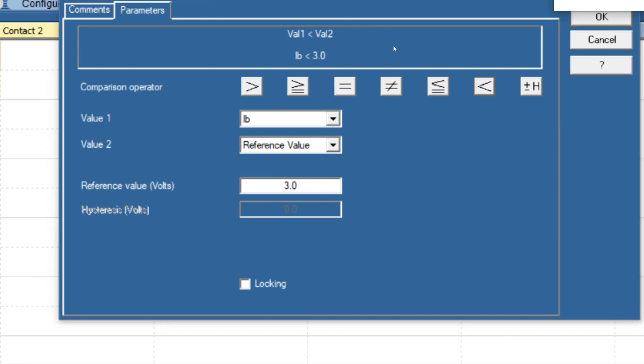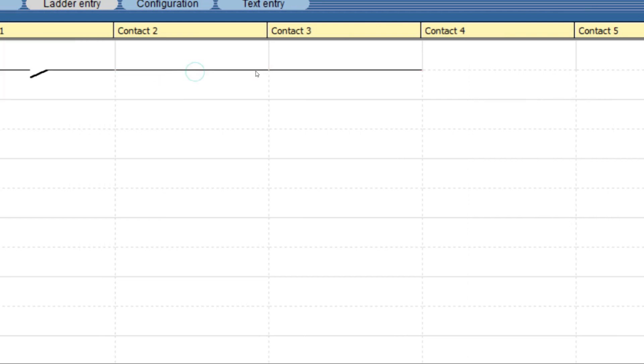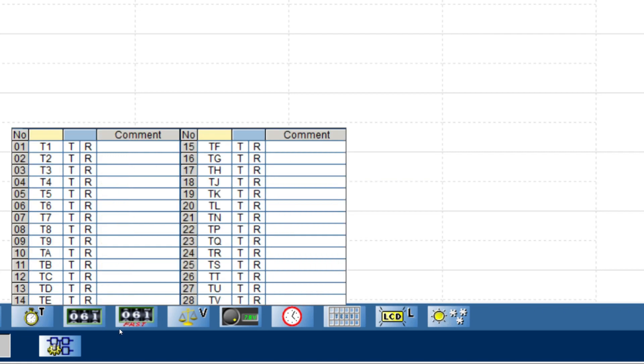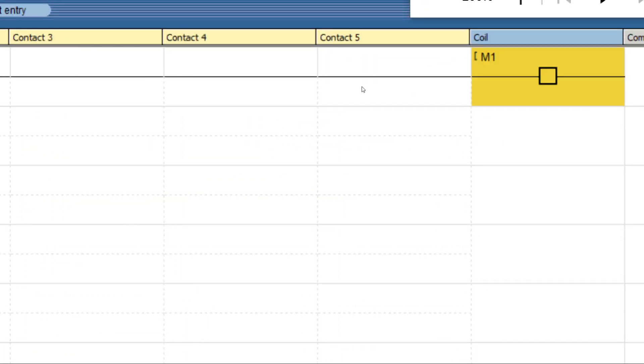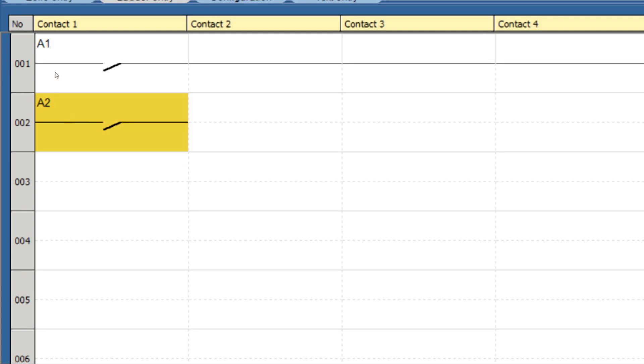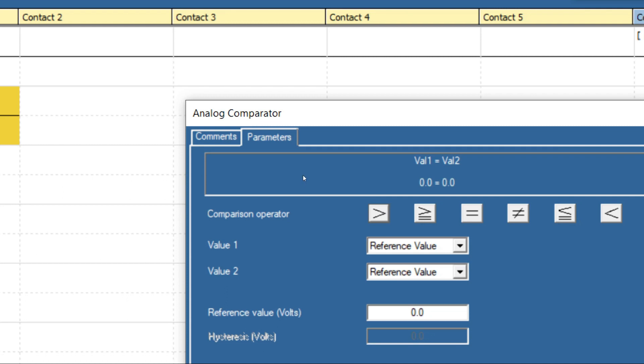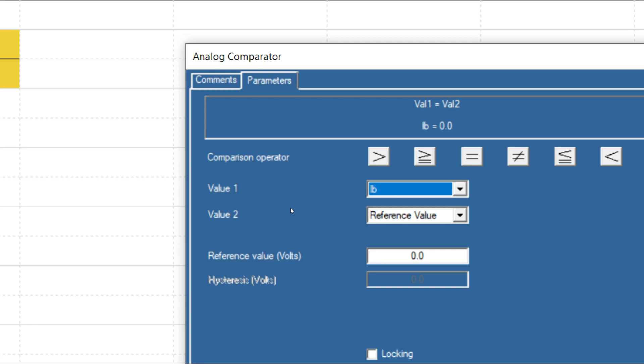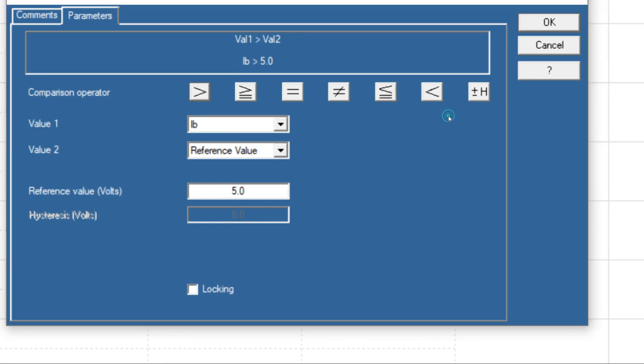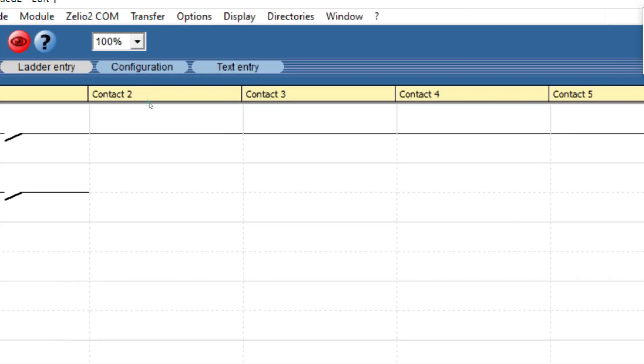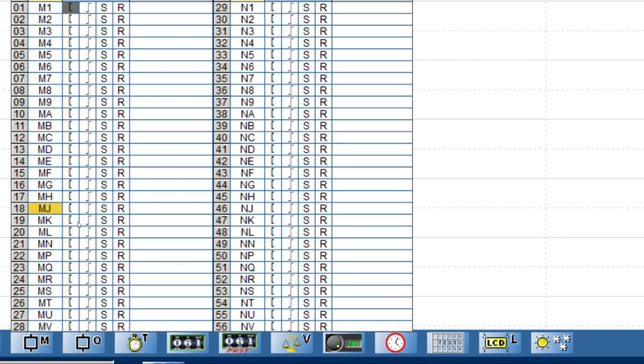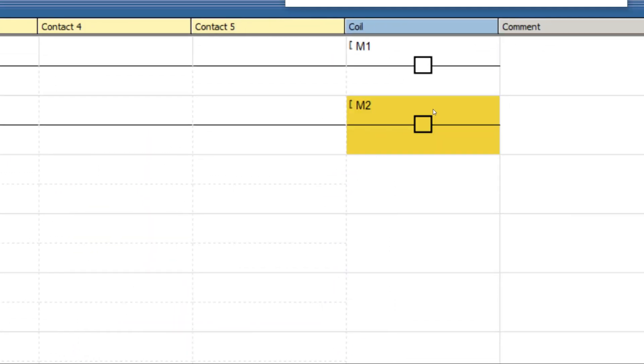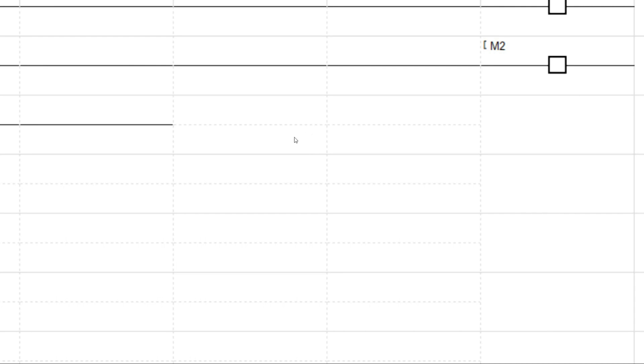We will keep one auxiliary, then we select another analog comparator. As I told, it should run till 5 bar, so input IB, reference value 5 volt. 5 bar means 5 volt, greater than 5 bar, so stop.